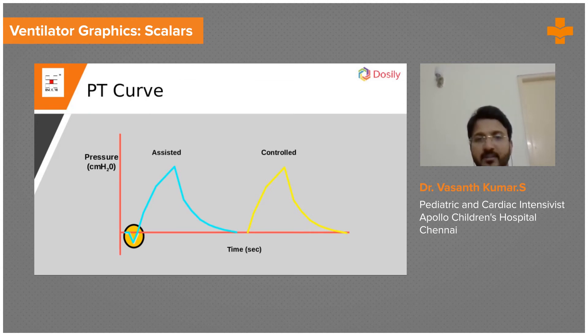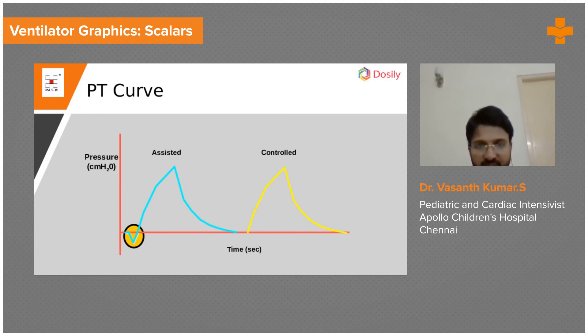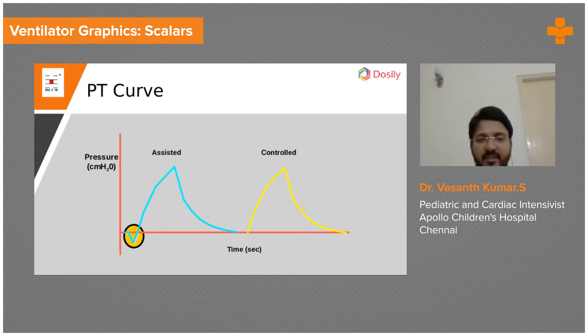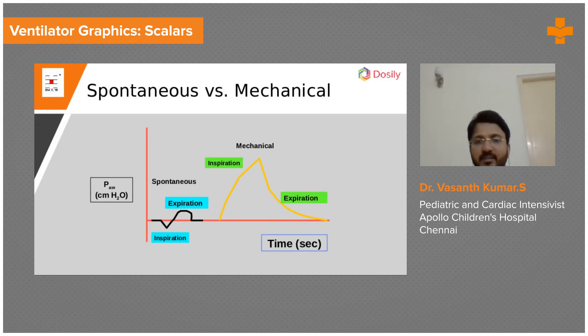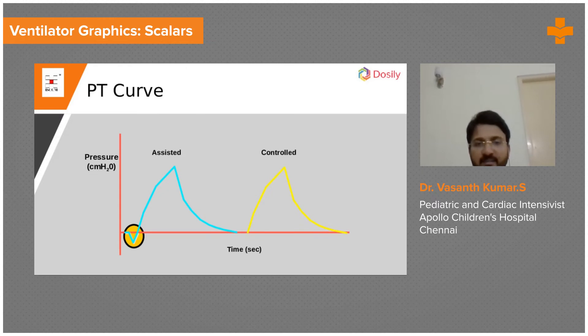This is a controlled breath and this is an assisted breath. The difference between an assisted breath and a controlled breath is that in an assisted breath, the patient is making the effort and triggering the ventilator, but the ventilator supports that respiratory effort. If the patient takes an effort, the ventilator rewards him with a breath. In spontaneous mode, everything must be done by the patient — the ventilator only partly supports him. In controlled breaths, the ventilator gives all the breaths. In assisted breaths, the patient just has to trigger the ventilator and the rest is given by the ventilator.